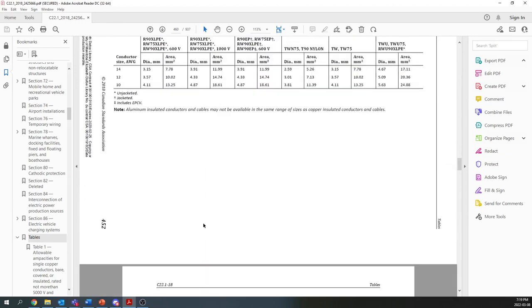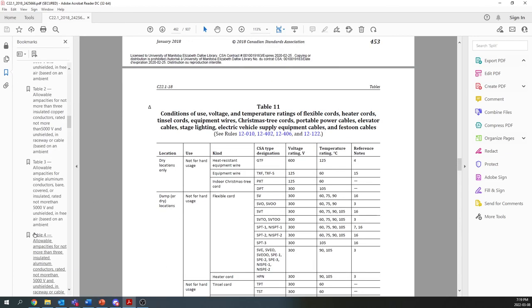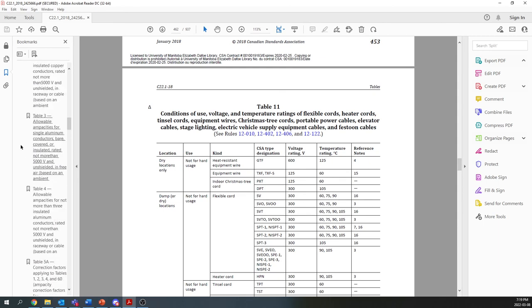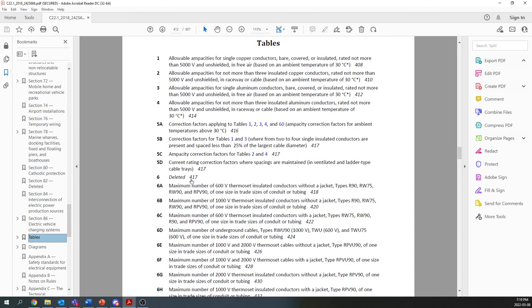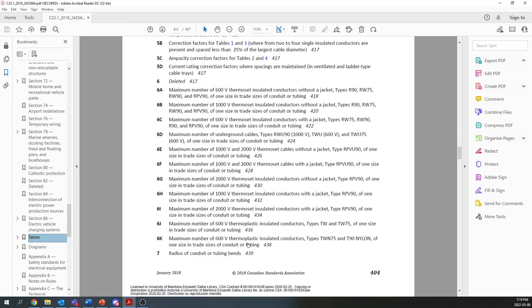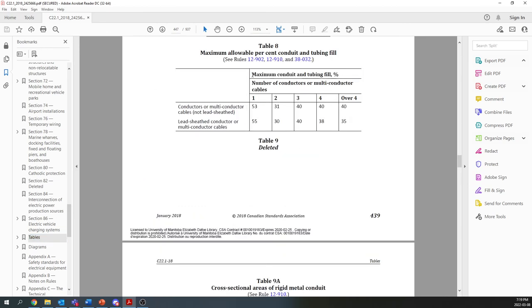So this is Table 8 from here. Now what I'm looking for here is, this is changed between this table and last table, but there's a derating table, like I had mentioned, here, Table 8. This is what I want: maximum percent conduit and tubing fill. So we have our number, let's just say 400 square millimeters, and we have over 4 conductors, so we don't have lead-sheathed. So this 400 square millimeters can only represent 40% of the size of the table. So if we size that up, divided by 0.4, we actually need 1,000 millimeters squared. That actually worked out pretty nicely. 1,000 millimeters squared worth of conduit size.